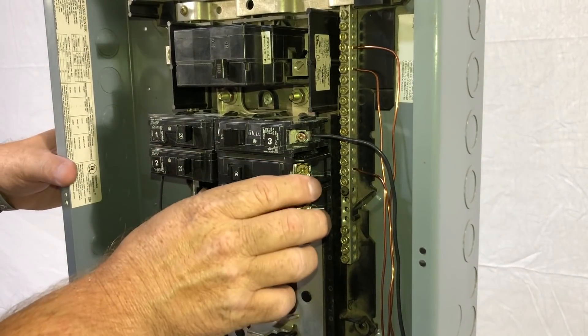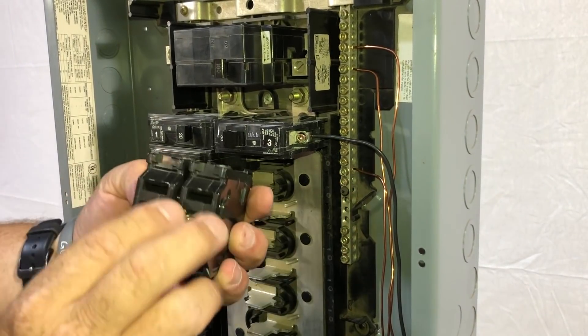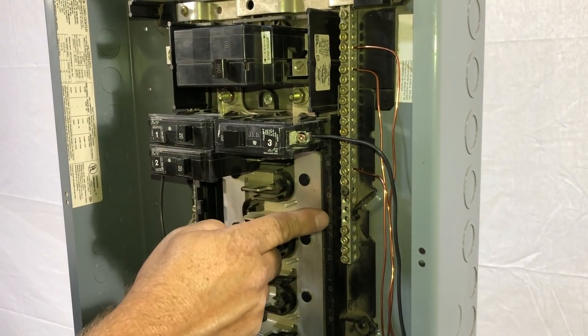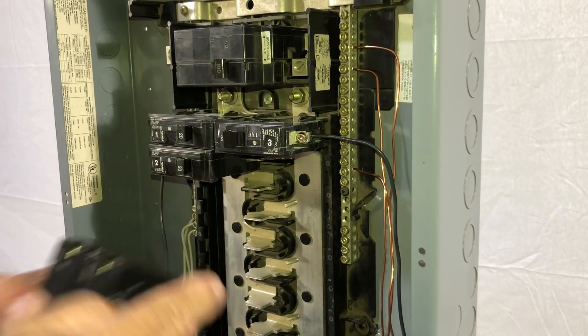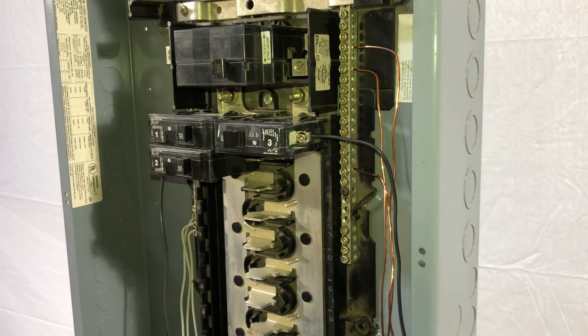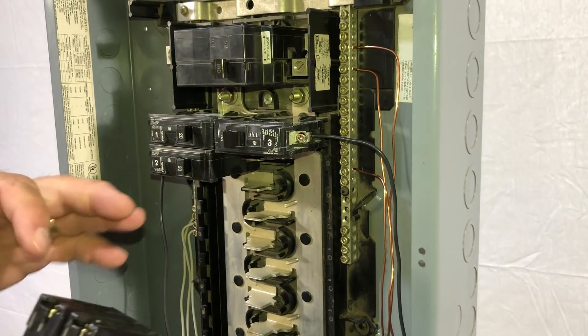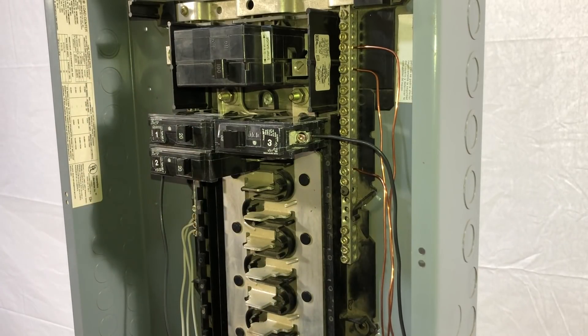Now grab the breaker and just pivot it out. You'll notice that it has these two notches — these notches go with the track system in the back portion. These are the terminals that are going to hit the spades inside the panel. That's where it picks up 110 from each side of the panel — 110 to each side of the breaker gives you 220.